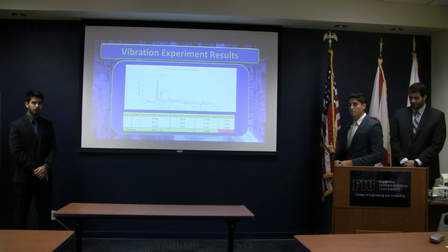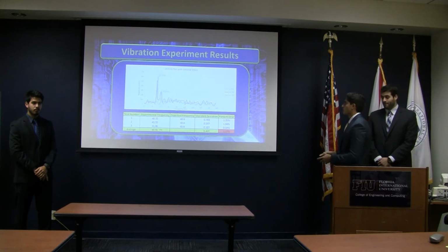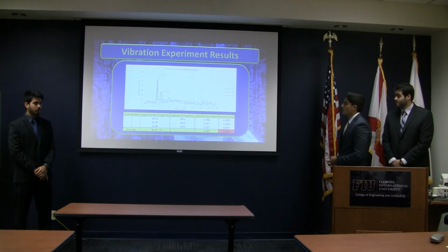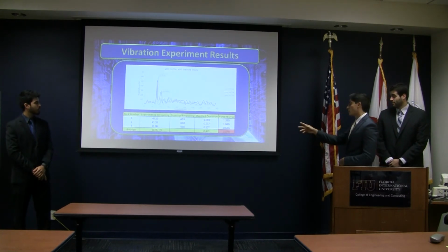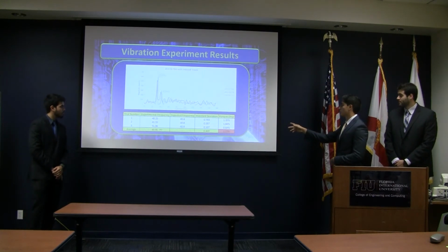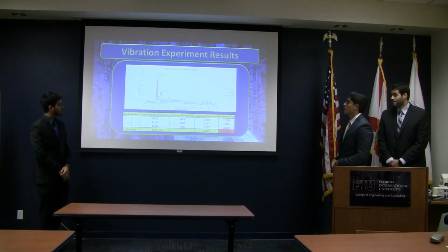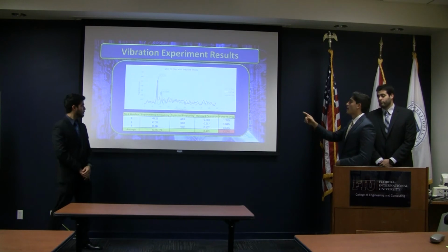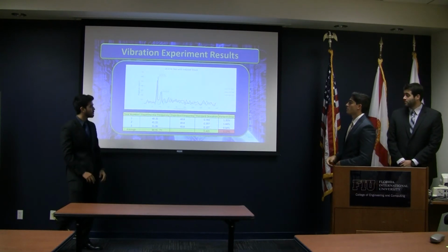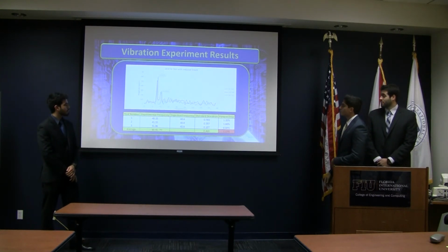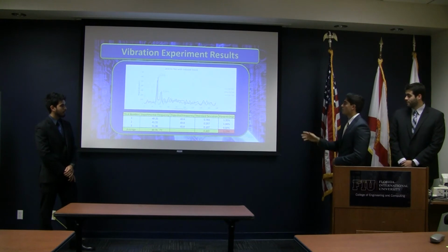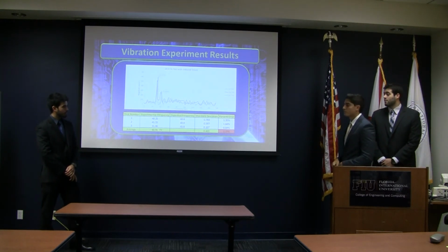Now the sound you hear is a motor with an induced knock. That experimental frequency was again very close, with a 1.27% error compared to our expected frequency. However, that induced knock had an amplitude of 600 millimeters per second squared, with a lower frequency of about 32.55 hertz.